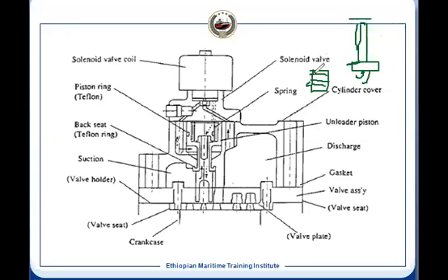and when the oil pressure comes, that time it closes so that it is in a loaded condition. It means this will push to keep open when we want to unload, and when the oil pressure comes and acts on it, it will remove from the position. For example, we apply oil pressure on this face. Then what will happen? This will have a movement down. So in that case, it will be in loaded condition.